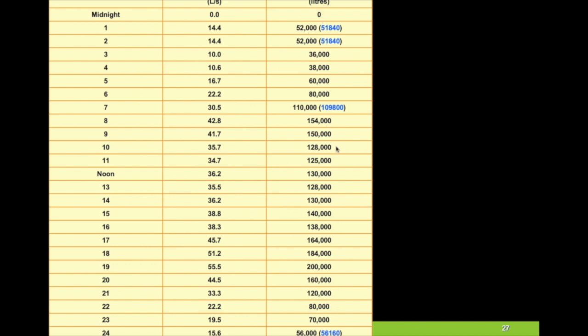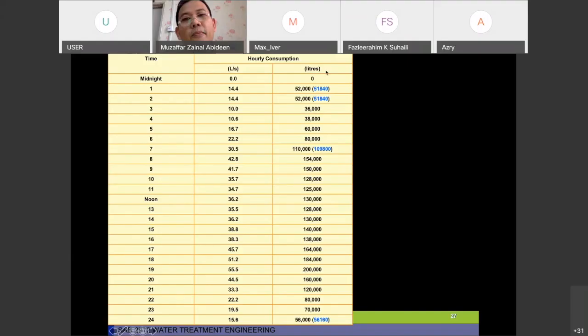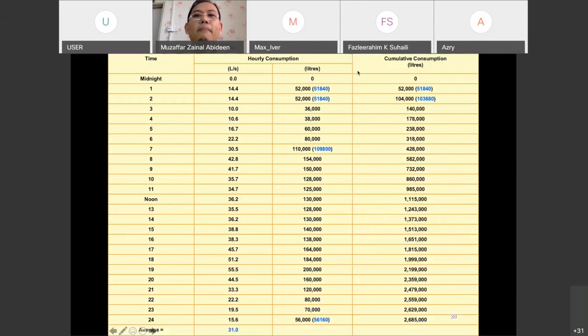If you want to know the volume being used from six o'clock to seven o'clock, they are using 30.5 liters per second. This value has to times 60 and times 60 to get the real volume being used for that one hour, which is 109,800 liters.